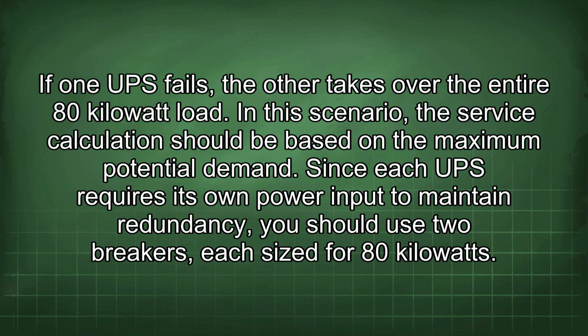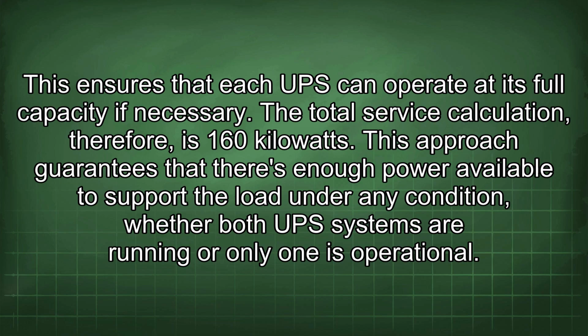Since each UPS requires its own power input to maintain redundancy, you should use two breakers, each sized for 80 kilowatts. This ensures that each UPS can operate at its full capacity if necessary. The total service calculation, therefore, is 160 kilowatts. This approach guarantees that there's enough power available to support the load under any condition, whether both UPS systems are running or only one is operational.